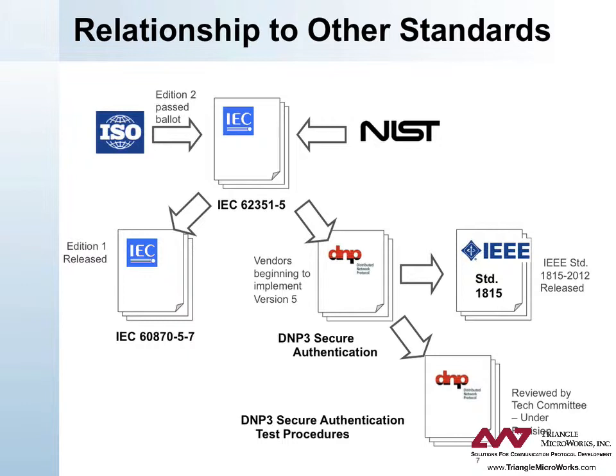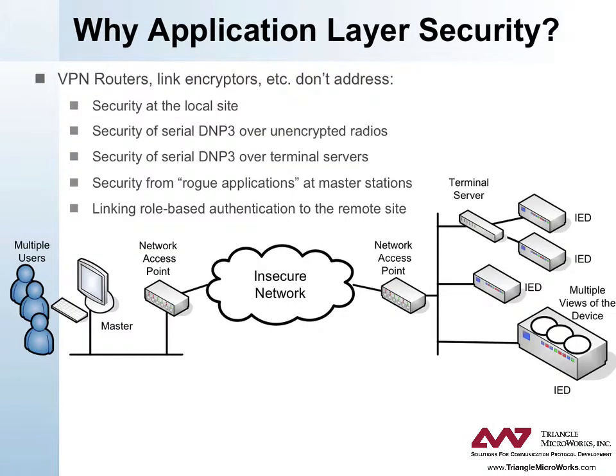IEC 62351-5 is in turn based on International Standards Organization, Internet Engineering Task Force, and U.S. National Institute of Standards and Technology standards. DNP3 is challenging to secure because it can be used in a variety of networks, including radio systems, serial links, and IP-based wide area networks. Furthermore, it is designed so that from one end of the network to the other, it may travel over more than one of these links. For this reason, DNP3 Secure Authentication is included in the topmost of the OSI layers — the application layer.